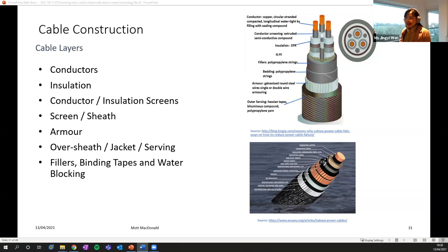Fourth, screen and/or sheath. This has three important functions. First, it provides a ground reference for uniform field distribution throughout the insulation. Second, it provides a hermetic seal against moisture. And third, it provides a dedicated path for fault current, therefore securing the operation of the protection systems and protecting the cable from excessive fault damage.